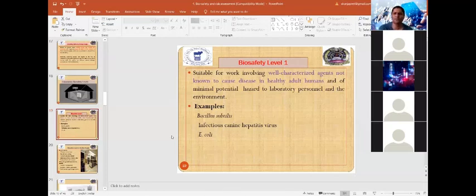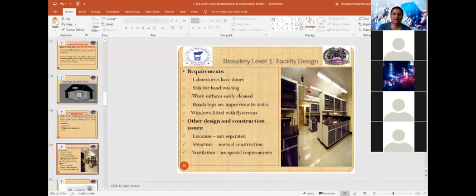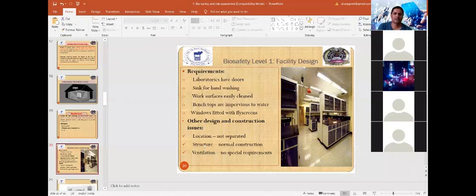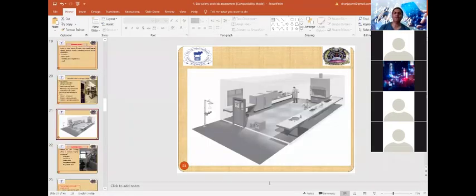Examples of BSL-1 organisms include Bacillus subtilis, infectious canine adenovirus, and non-pathogenic Escherichia coli. BSL-1 laboratory facility design includes doors, a sink for handwashing, work surfaces made of easily cleaned materials, impervious bench tops, and windows fitted with fly screens. No special separate location or ventilation is required.